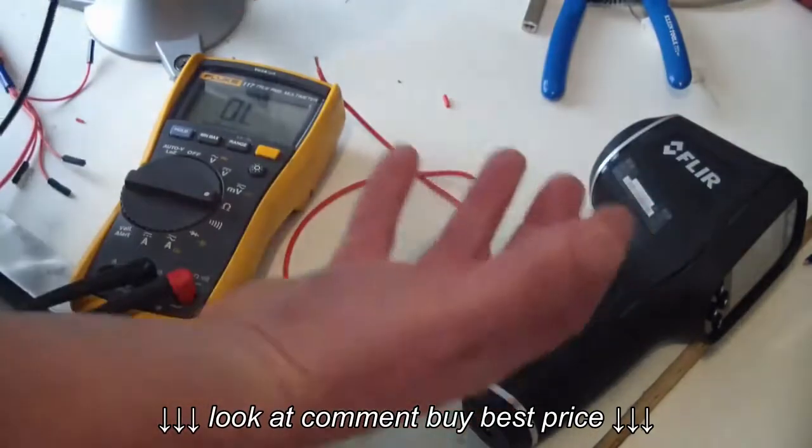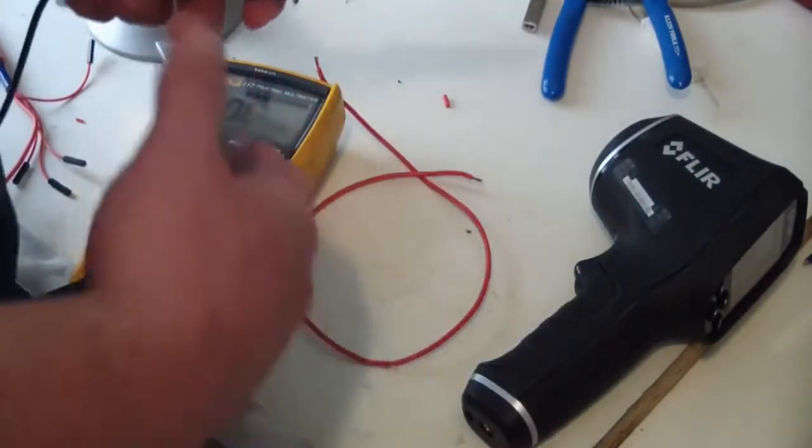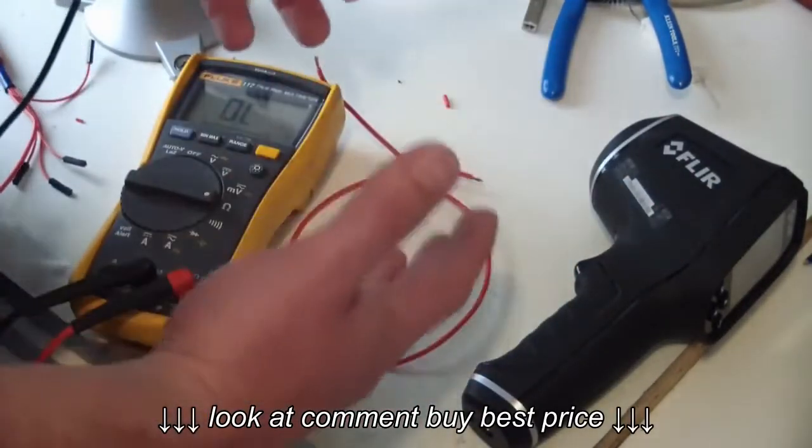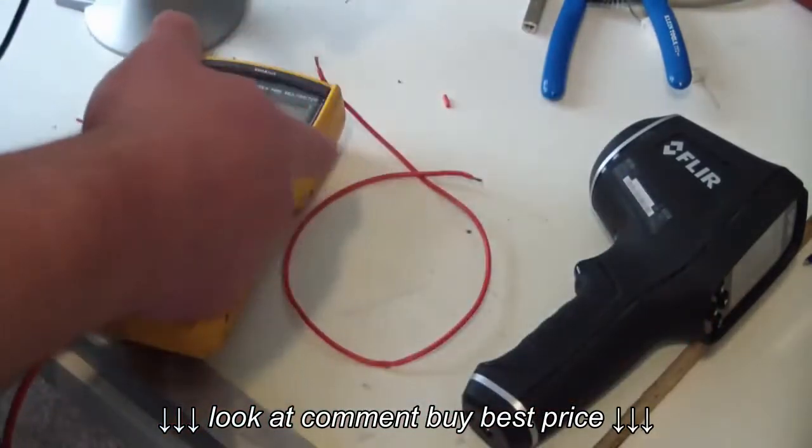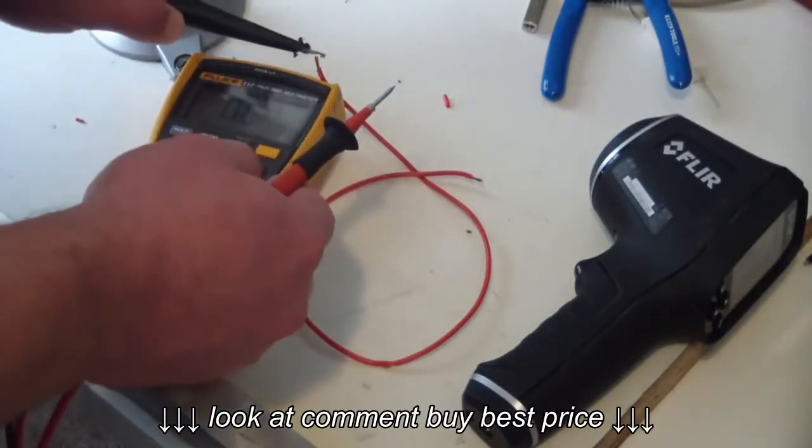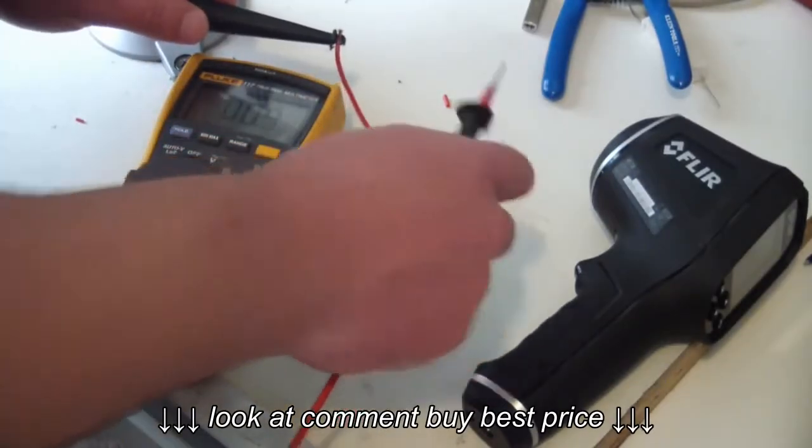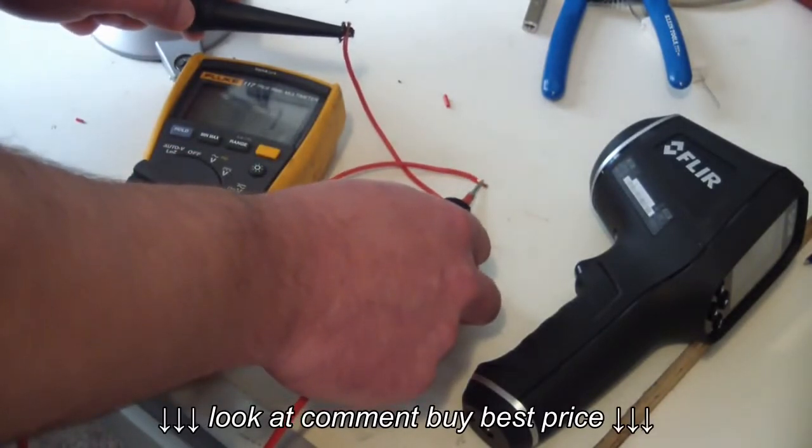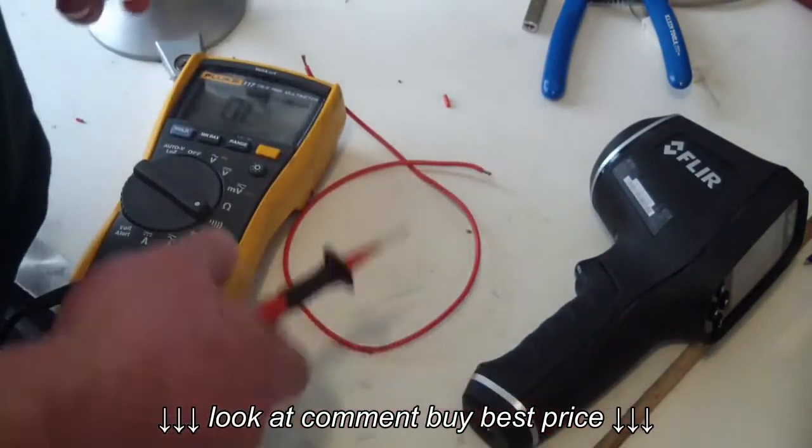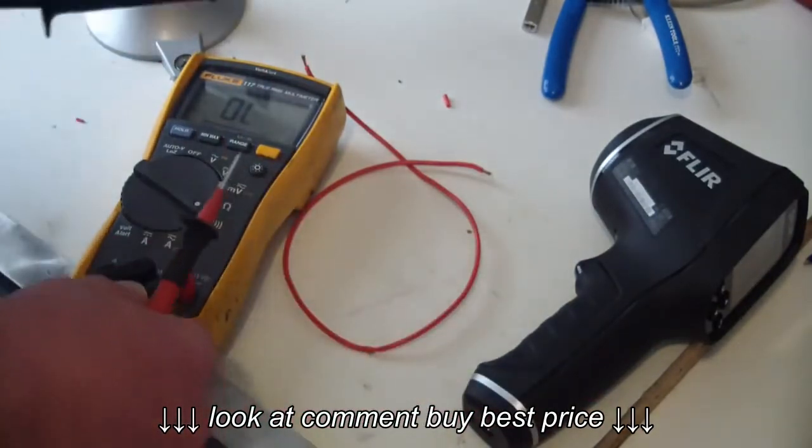Also, you could progress and do a voltage drop across that. But of course, the thing has to be energized in order to do a voltage drop. So we're just going to ohm it out. Make sure that it's got good continuity. 0.4 ohms. And if you were on your continuity test, if you were someplace quiet, like the bench, you'd be able to hear that, and there's continuity there. So you'd move on to another part of the circuit because this is obviously good.